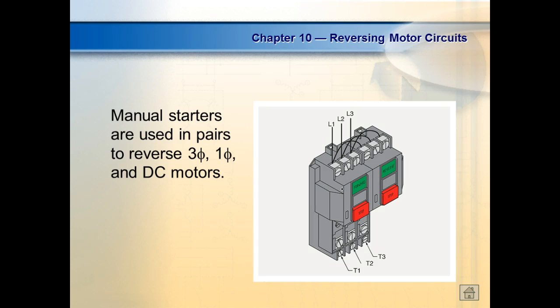So we do have manual reversers. This is what they're showing here. This is actually a motor starter. What makes it a motor starter and not a contactor? It's got an overload. This is for three-phase, by the way. And for these motor starters, or these contactors, this is the industry standard: we bring power in the top, and then we hook our motor at the bottom of the relay. So all these relays are going to be mounted vertical. Up here on your three-phase motor starter, they're going to be labeled L1, L2, and L3. And down at the bottom, it's going to be labeled T1, T2, and T3. That's just the way industry does these contactors. Then I'll show y'all. Are we okay?